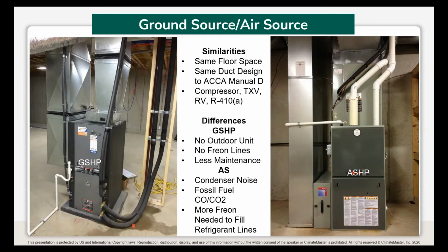The photo on the left has exactly the same ductwork, because we design using the same CFMs per ton. And then we have what looks like a gas furnace, but in fact is the entire ground source heat pump box. In the bottom of that box, we have a compressor and the electric components. In the top half of that box, we have the air delivery system, or the motor and the blower assembly. Everything that you use to heat and cool that structure is in that box, so no outdoor unit is needed. Those black rubber tubes that run from the piece of equipment up to the ceiling and then outside are high density polyethylene pipe and are connected to the ground loop of the geothermal system.